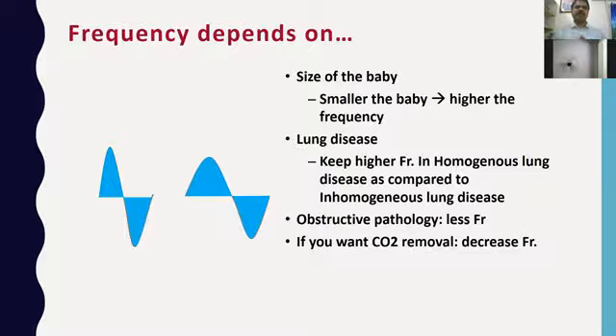This is in sharp contrast to your conventional ventilation. In conventional ventilation, what we are generally taught is that if you increase the frequency, the minute ventilation will increase, so CO2 removal will be better and CO2 will drop. Whereas in high frequency, this is quite the opposite. If you reduce the frequency, there will be a longer time for the gas exchange to occur, so there will be better CO2 removal. So if you want CO2 removal, you keep a lesser frequency.